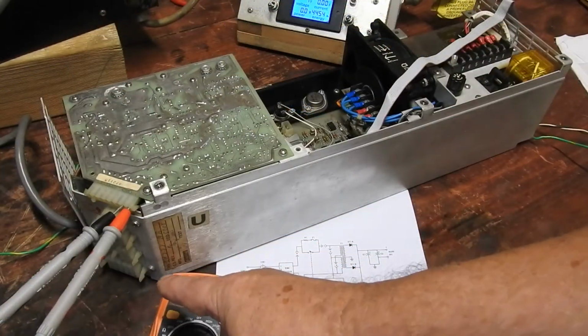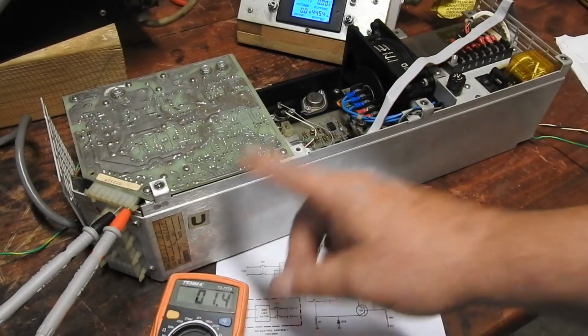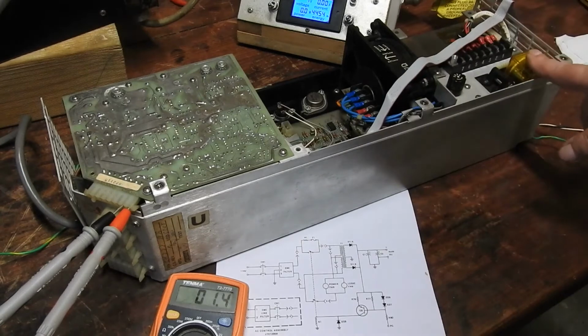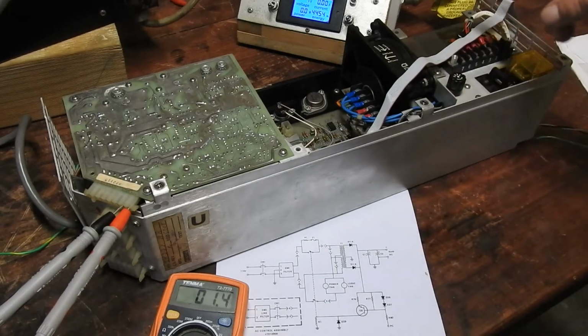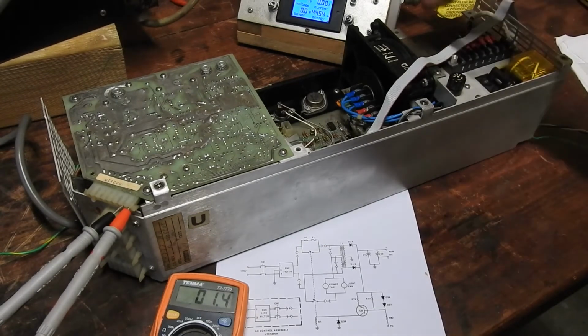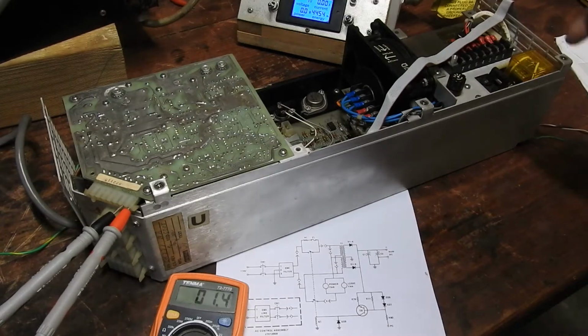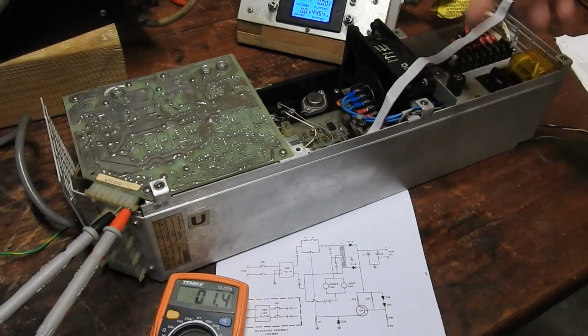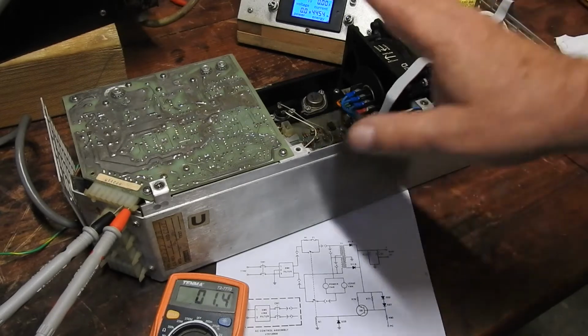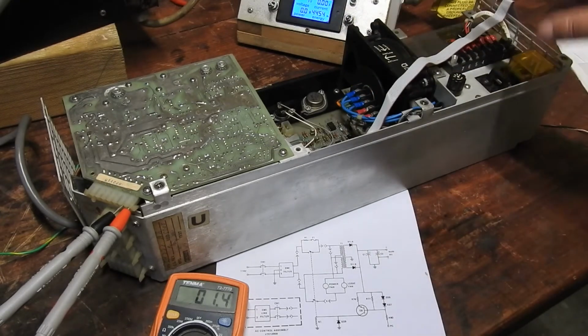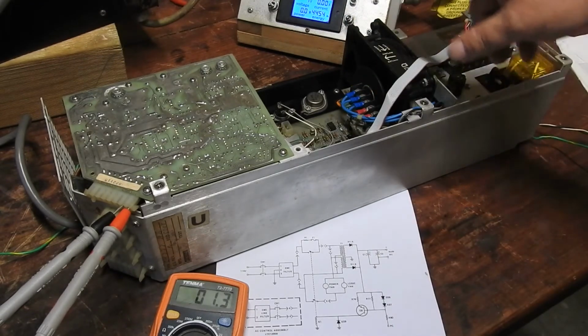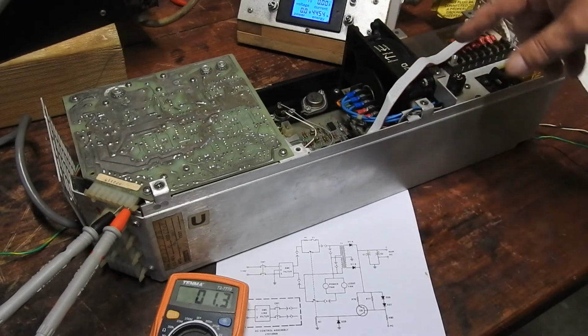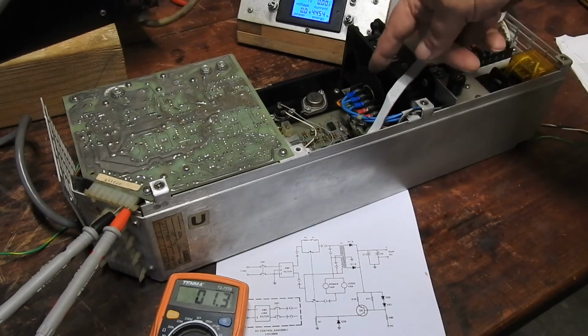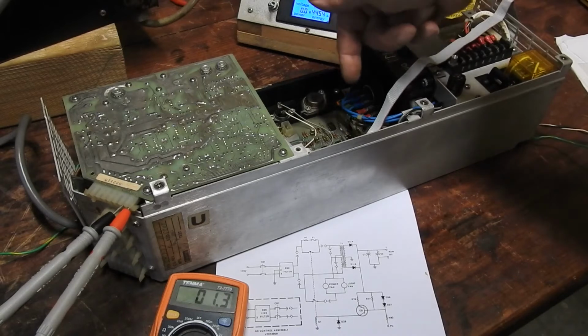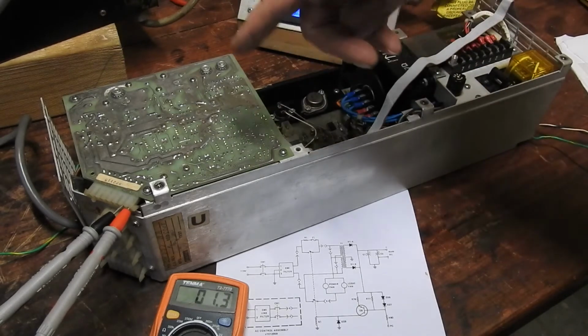But no smoke either, that's a good sign. We saw no voltage coming out of there. The fans aren't turning because the relay hasn't picked. The transformer's running via a resistor, a power resistor down in the guts there, that gives it a bit of power, but until the relay is picked, the mains voltage doesn't go to the fans, and the rectified raw voltage from the big capacitors on the back doesn't get into the regulators.